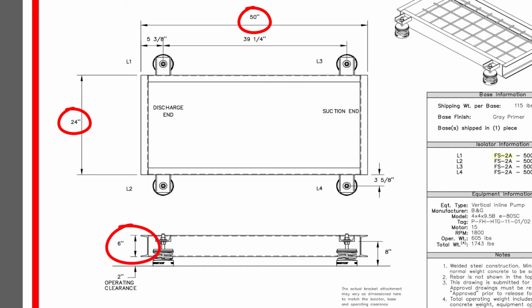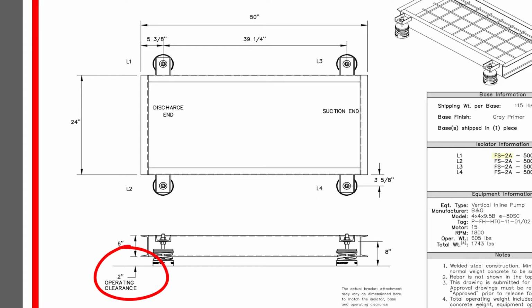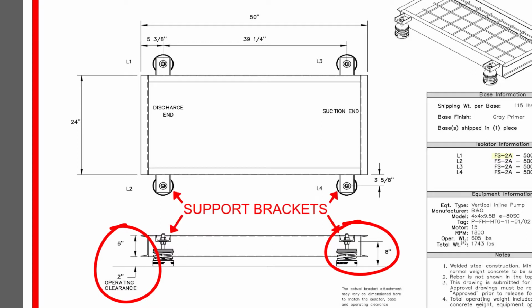Inertia bases must have an air gap beneath them that is large enough to minimize the air piston effect and to allow easy inspection and removal of any debris that may short-circuit the vibration isolation. This base is designed to have a 2-inch air gap underneath. You can add the operating clearance to the base thickness and compare the result with the operating height for the isolator support point and determine where the support brackets will be.